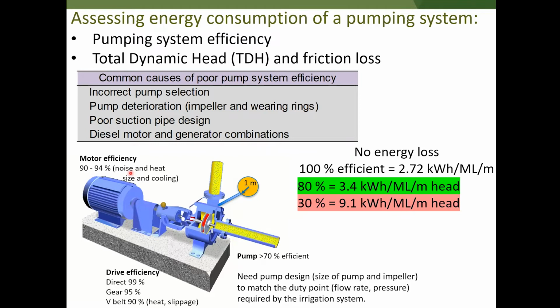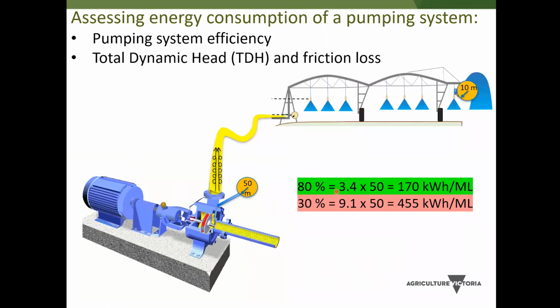The other big common cause of poor pumping system efficiency is where we don't have mains electricity. We've got a diesel motor and generator providing electricity to the motor, and there's inefficiencies in that diesel motor and generator. And if that's not sized correctly, it can have low load on it, and that can result in very poor efficiencies, and that is actually what was causing this 30% efficient system. We'll also have a look at that at Sam's situation. It's not quite as bad, but that diesel motor and generator is causing some issues. So that's just the pumping system.